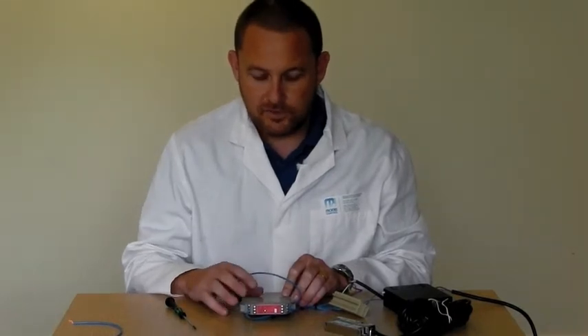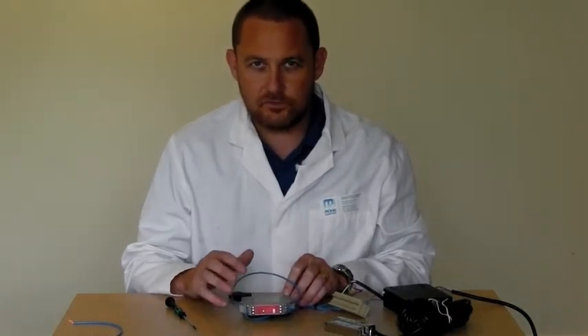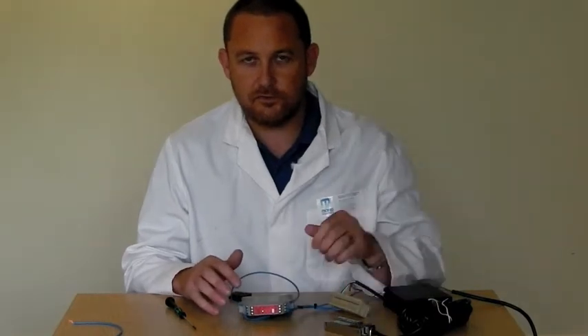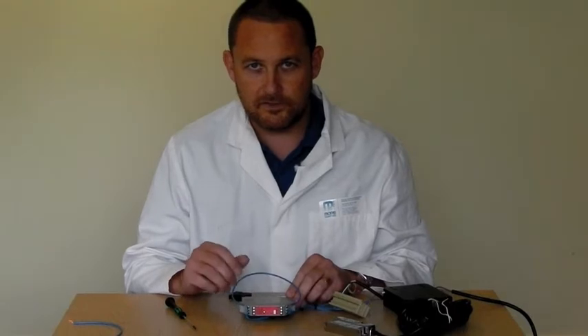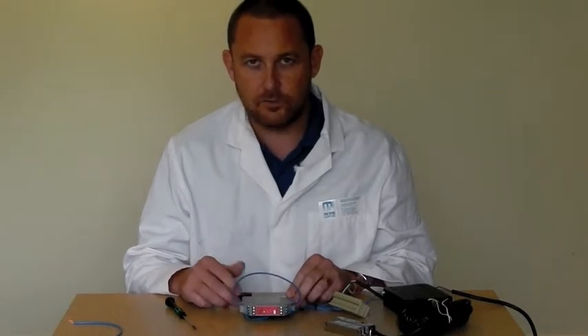The reason is that the safety relay looks for both channels or both circuits in the safety switch to close within a very small space of time, and they didn't, so the safety relay has gone into a lockout condition.